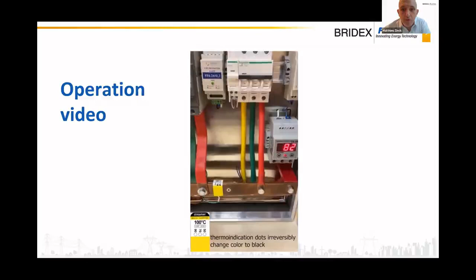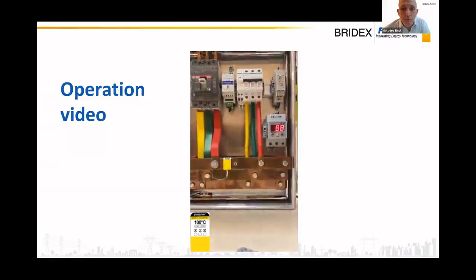At 90 degrees, there will be the third thermodot turning black. So we're reaching little by little this 90 degrees. Now we reach 90 degrees, the thermodot has turned black. And then by 100 degrees, there's a LED on the sensor that will turn red on the top sensor, and the breaker will trip. Yes, so the dry contact output of the sensor, now I will show you here. Up here, the LED has turned green, and the dry contact of the sensor has closed, leading to the trip of the breaker.